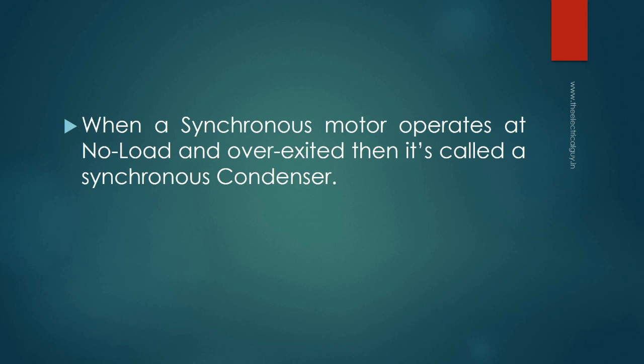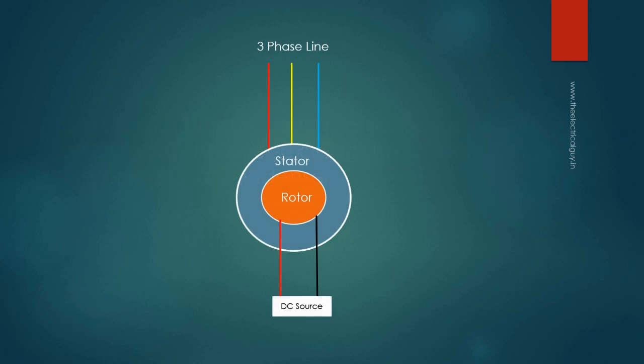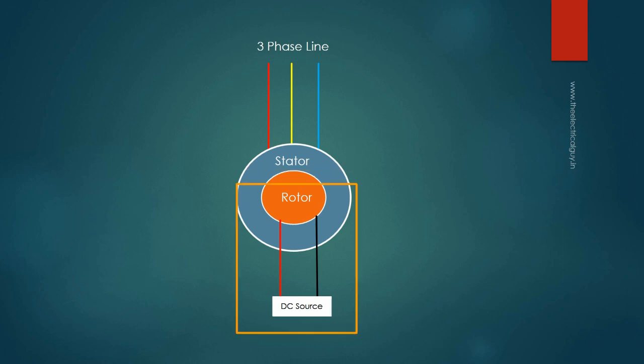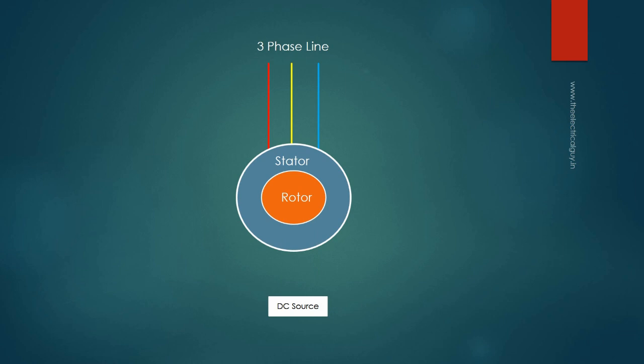The MMF needed to produce the constant flux phi may be produced by either the stator — connected to a three-phase line — or by the rotor — excited by a DC source — or by both. If the rotor excitation current is zero, all the flux has to be produced by the stator alone, and hence the stator must absorb reactive power from the three-phase line.